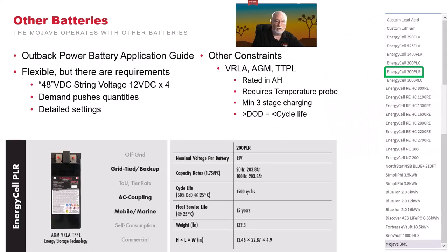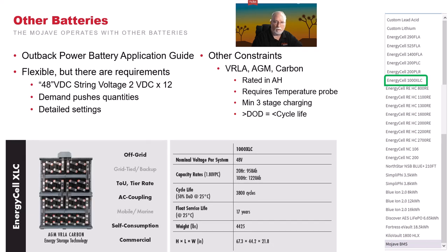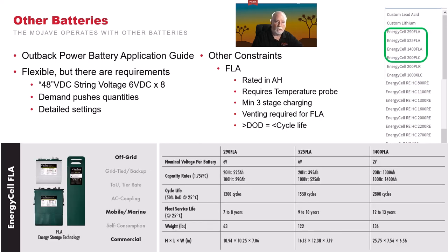So other batteries, just taking a look at them, we have a lot here. Like I said, Mojave's flexible. This is an example of the Energy Cell PLR. It's a VRLA, AGM, TTPL battery. It's rated in ampere hours. Again, minimum 3-stage charging. And again, the higher you take them in discharge, the shorter their life cycle. We also have the Energy Cell XLCs. Again, these may already be in place. All you have to do is go to the drop-down. You can effectively connect to these.